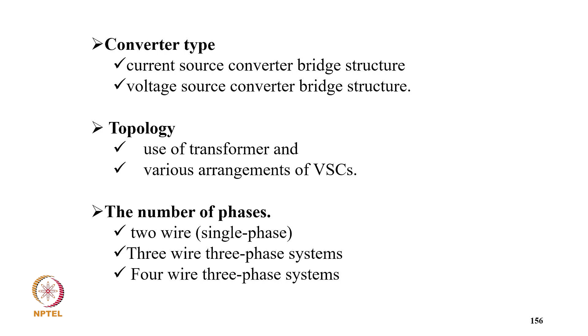Now converter based classification, and a typical example is the current fed type of D-STATCOM. So here we are using a current source converter, and of course, because it will be generating pulsating current, you need a capacitor to work as a filter for lower order harmonics. And on the DC link you need an energy storage device, so here you need the inductor as the energy storage device. Because of this reason this topology is not preferred, because on the DC link you need the inductor, it is costly, bulky, and lossy. On the AC side you need the extra capacitor.